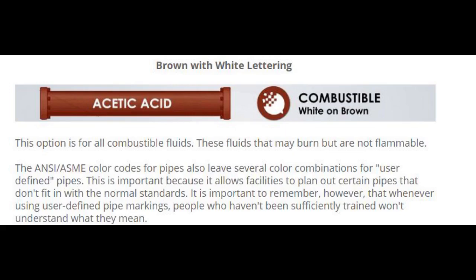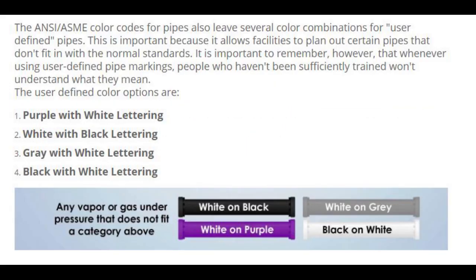Now let's talk about user-defined colors. The ANSI and ASME A13.1 color codes for pipes also leave several color combinations for user-defined pipes. This is important because it allows facilities to plan out certain pipes that don't fit in with the normal standards. It is important to remember, however, that whenever using user-defined pipe markings, people who have not been sufficiently trained would not understand what they mean. The user-defined color options are: purple with white lettering, white with black lettering, gray with white lettering, and black with white lettering.